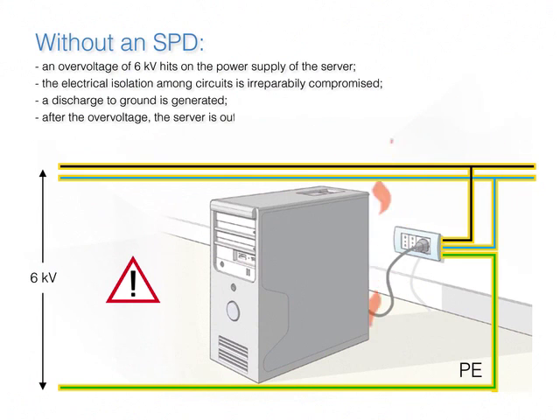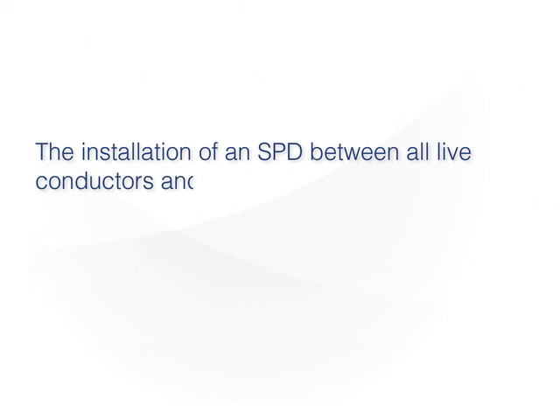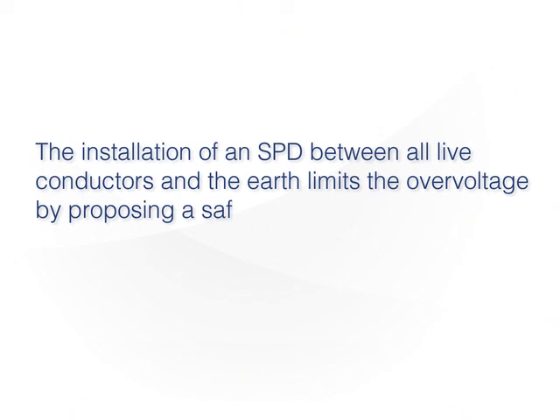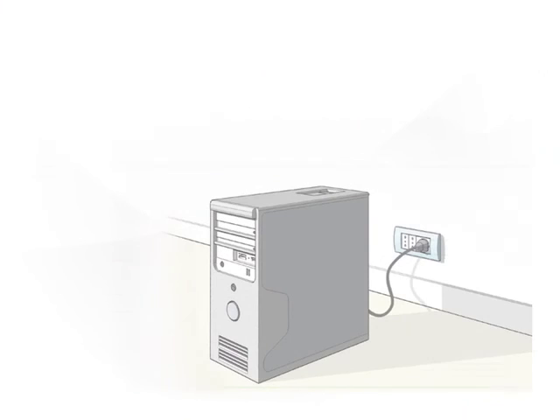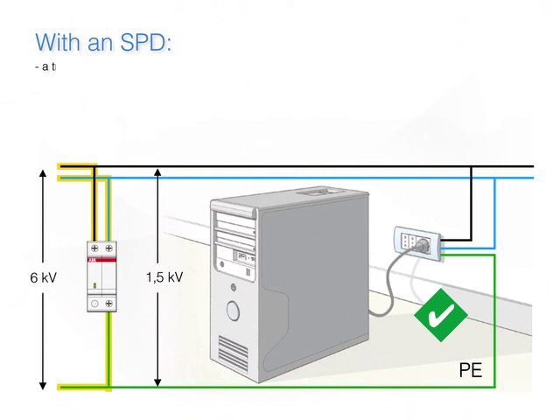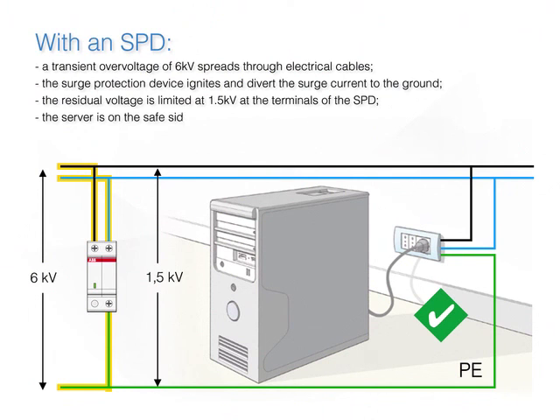After the overvoltage, the server is out of service and a risk of fire is present. The installation of an SPD between all live conductors and the earth limits the overvoltage by proposing a safer path and diverting it directly to the ground. With an SPD, a transient overvoltage of 6 kV spreads through electrical cables. The surge protection device ignites and diverts the surge current to the ground. The residual voltage is limited at 1.5 kV at the terminals of the SPD, and the server is on the safe side and protected from the overvoltage.